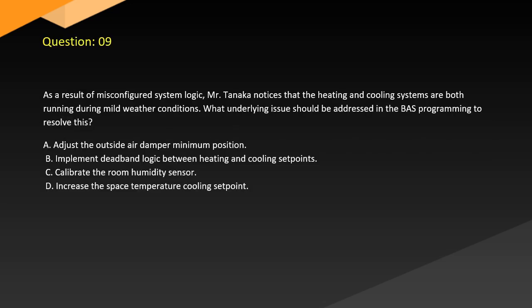Question 9. As a result of misconfigured system logic, Tanaka notices that the heating and cooling systems are both running during mild weather conditions. What underlying issues should be addressed in the BAS programming to resolve this? A. Adjust the outside air damper minimum position. B. Implement deadband logic between heating and cooling set points. C. Calibrate the room humidity sensor. D. Increase the space temperature cooling set point.